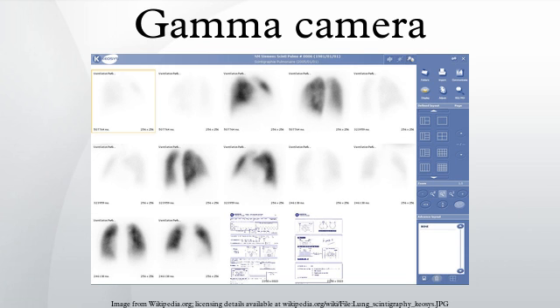The electronic circuit connecting the photodetectors is wired so as to reflect the relative coincidence of light fluorescence as sensed by the members of the hexagon detector array. All the PMTs simultaneously detect the same flash of light to varying degrees, depending on their position from the actual individual event. Thus the spatial location of each single flash of fluorescence is reflected as a pattern of voltages within the interconnecting circuit array.